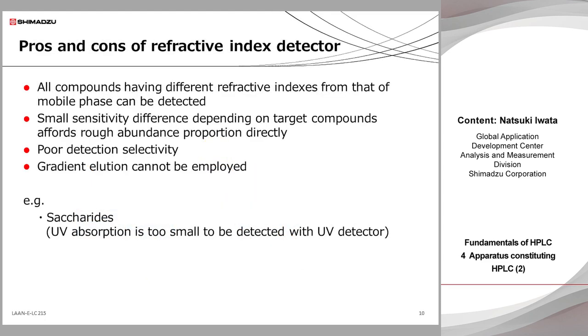In this slide, pros and cons of the RID are listed. The RID is called a universal detector, because all compounds that show a different refractive index from that of the mobile phase can be detected in principle. It is sensitive to coeluting interferences due to its non-selectivity, and also sensitive to temperature and pressure fluctuations. By contrast, the RID shows small sensitivity difference depending on the target compounds. This feature affords a rough abundance proportion of sample components directly, so the RID is commonly used in GPC analysis for calculating molecular weight distribution. Its sensitivity is generally worse compared to that of the UV detector. Gradient elution cannot be employed due to greatly changing refractive index of mobile phase. RID is commonly used for saccharides that have no UV absorption.